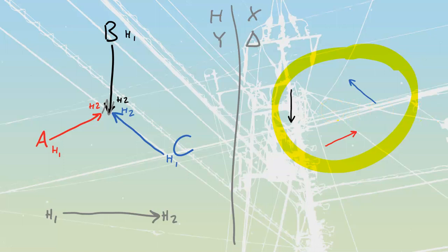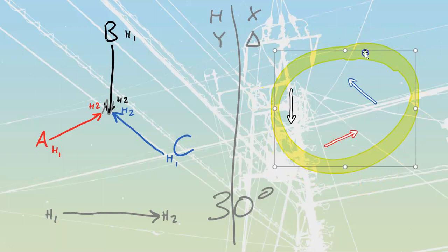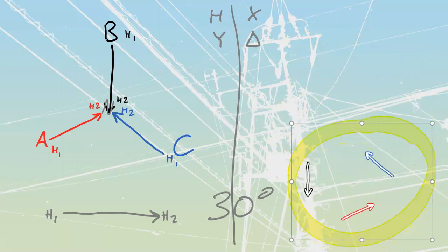Now we are going to have what's referred to as a 30-degree phase shift. And we are always going to have a 30-degree phase shift anytime that we move over from a Y to a delta. The direction that that phase shift is going to go in is always going to go up. So right now, we're just going to grab a whole pile of these here and move them out of the way. And then we're going to draw in where our neutral actually needs to be.